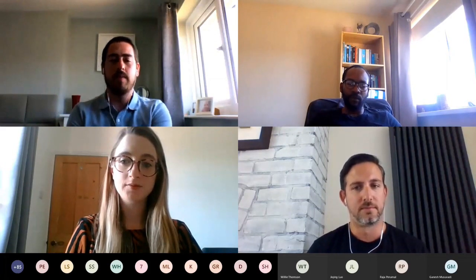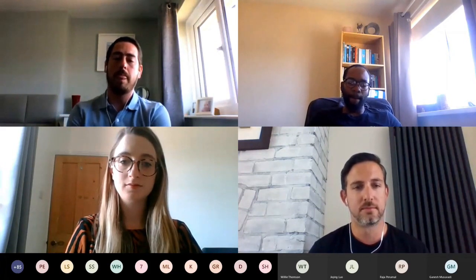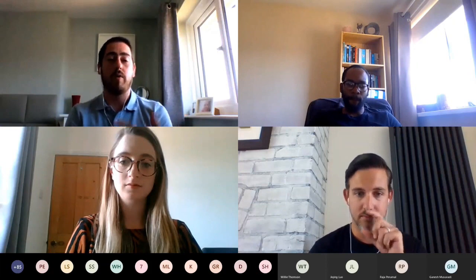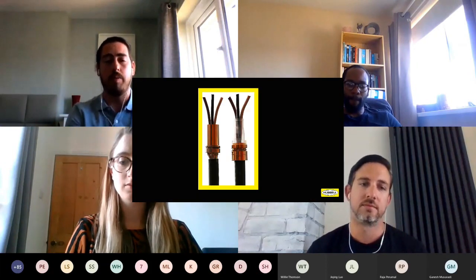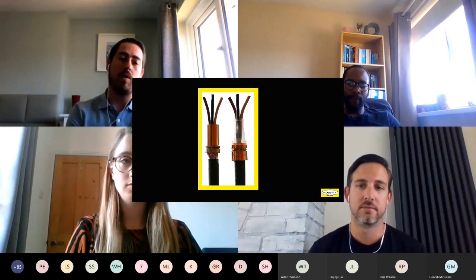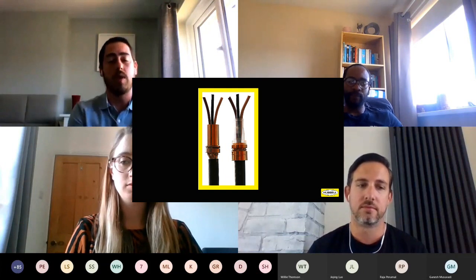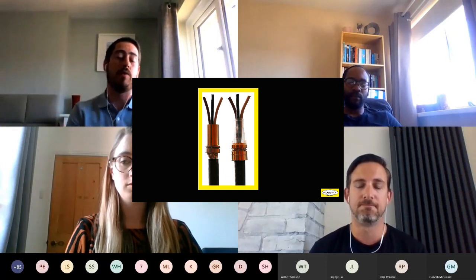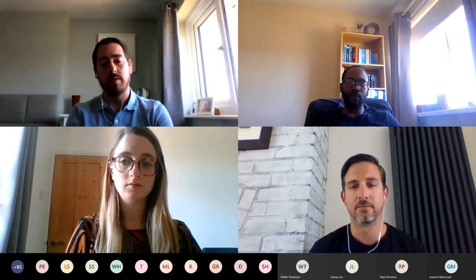With the addition of this new resin and this clear compound chamber, we've managed to pass all tests for NEC requirements, giving the very first transparent, clear, see-through compound pot that allows people in the NEC world to have some kind of inspectability, rather than it just being a brass component where you can't see where you're filling or how it's filled. That process makes things a lot easier.